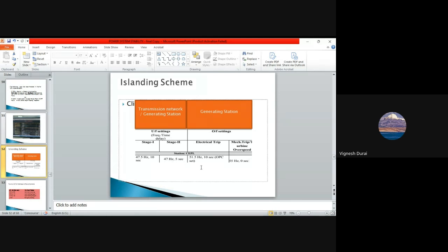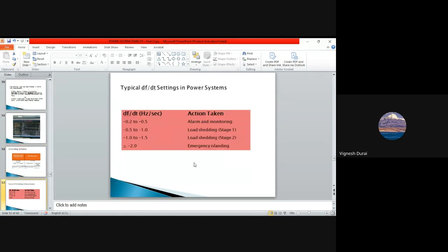And if your frequency is going above 51.5, immediately we have trips for tripping your generation stations. Okay, so that if you are generating more but your demand is less, your frequency will shoot up. For that, again they have trippings for your generation stations. Okay. For the islanding scheme, we have this df by dt also. If the frequency is dropping drastically, then again islanding will happen. Okay.